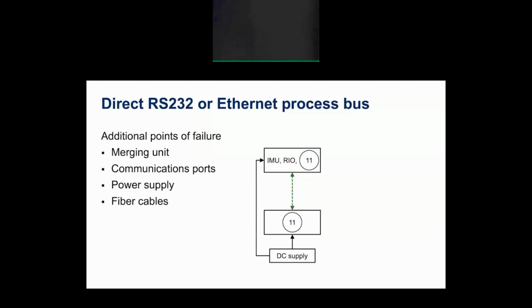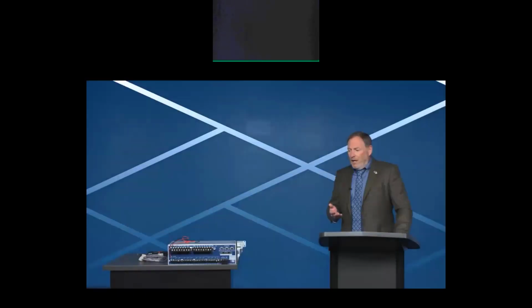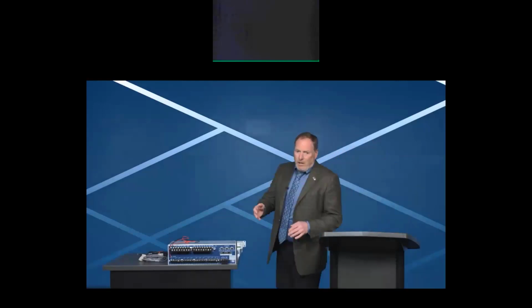So here we show an American National Standards Institute, ANSI, standardized numeric code 11, where device number 11 is for a multifunction intelligent device that does protection logic and probably other things like reclosing and so forth. The IEEE abbreviations for IMU, or Intelligent Merging Unit, which is a merging unit that does the A to D but also has intelligence like protection logic, or remote IO, which does not have intelligence. At SEL, we build all of these devices, and we build merging units to relay standards for the appropriate availability.